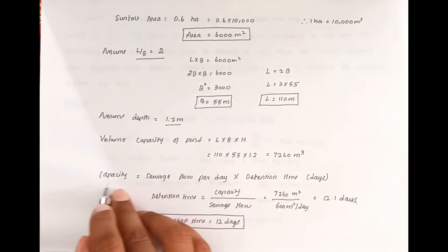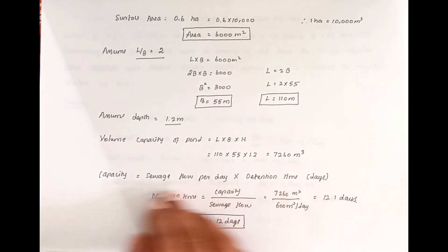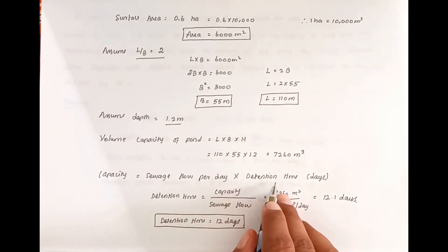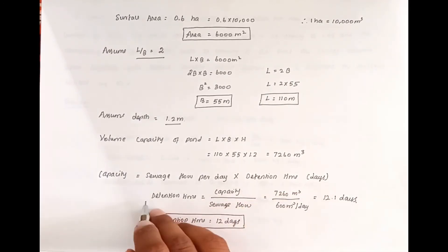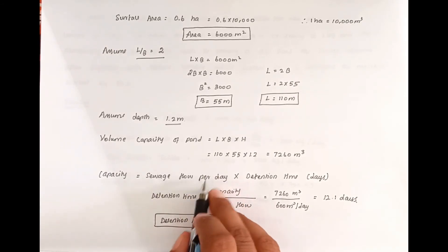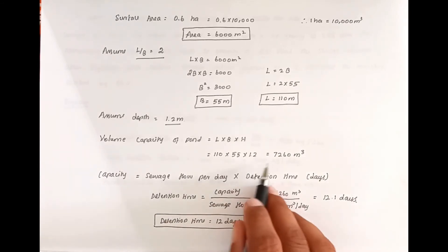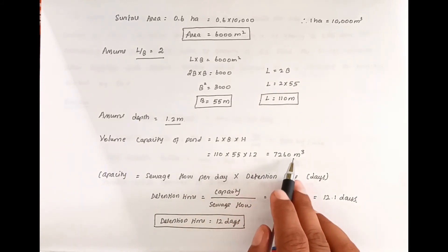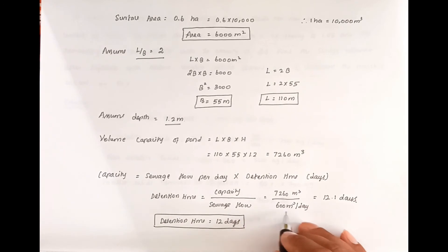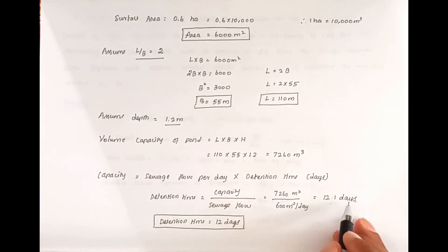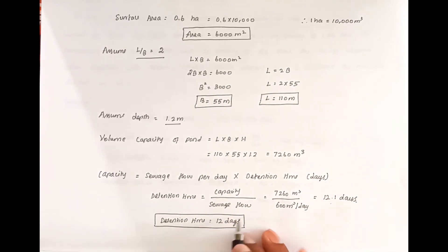Next, we calculate the detention period. Capacity equals sewage flow per day multiplied by detention time. So detention period equals capacity divided by sewage flow per day: 7260 m³ divided by 600 m³ per day equals approximately 12.1 days. Therefore, the detention period is 12 days.